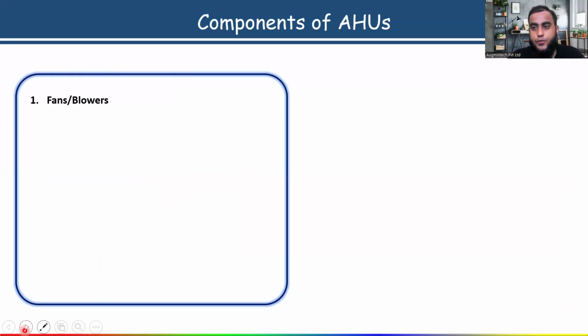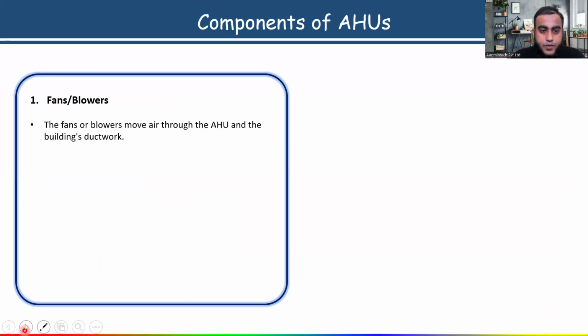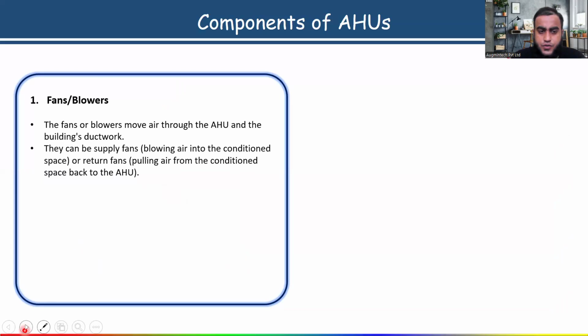So here the first component, as I showed you in the image, is what? Fans or blowers. All of you know that the fans or blowers generally move air through the AHU and the building ductwork. So they can be a supply fan or a return fan. Okay, sometimes in the return air duct also, on the return side also, we have to install a fan.